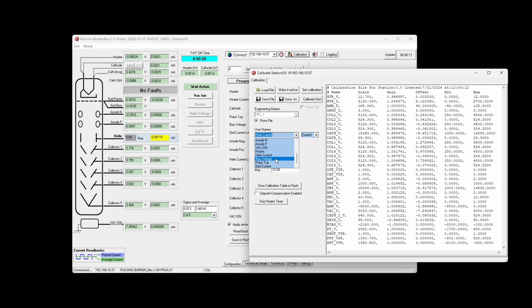Additionally, we're going to be calibrating bias voltage, which is set to -1 and 0. Based on some math internal to the unit, the gain has to be negative. And pulse top is 1 and 0. So we have verified that the three calibration factors that we're setting today are correct. Let's start with bias and pulse top.